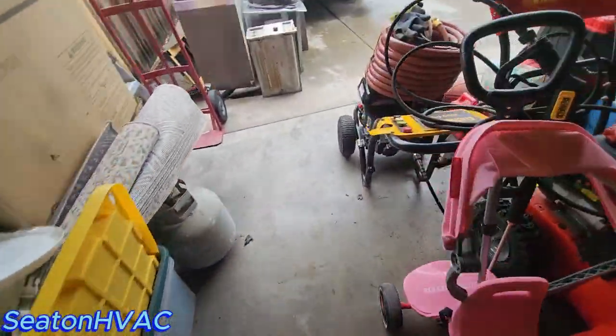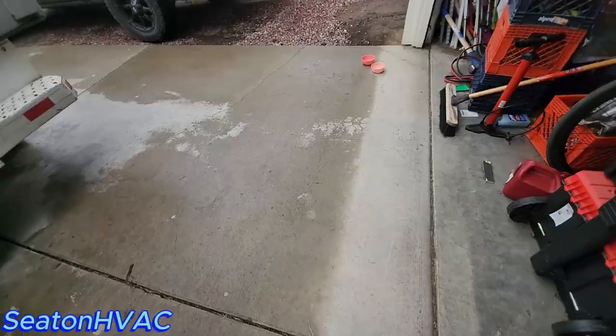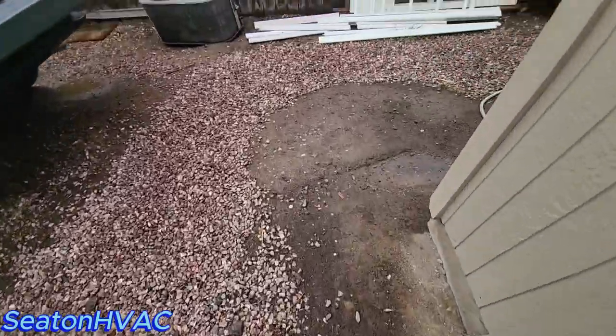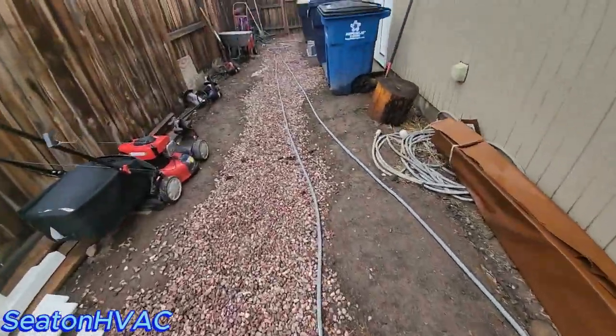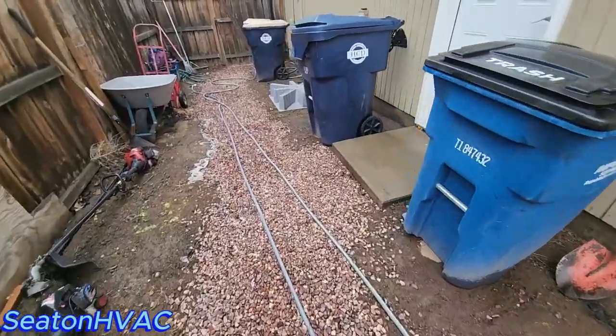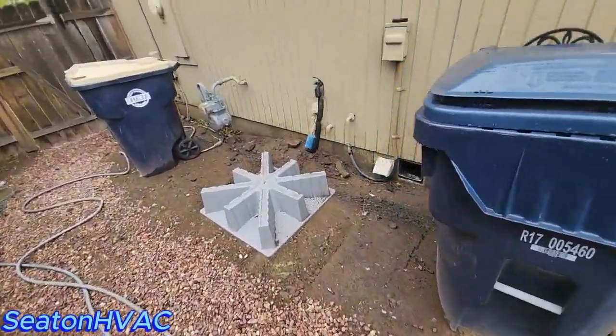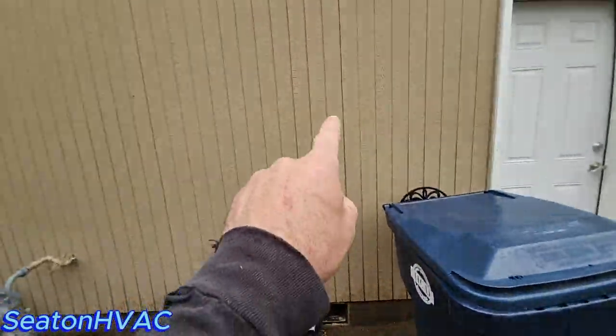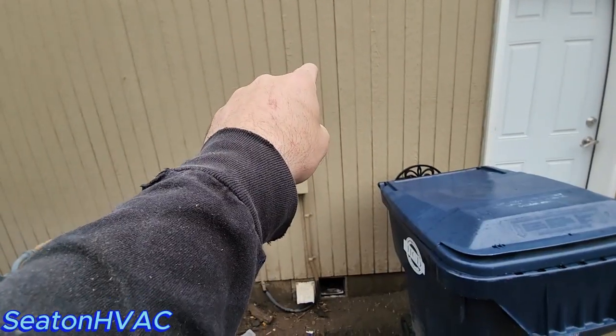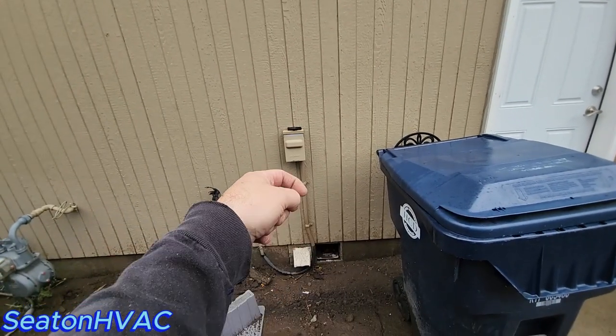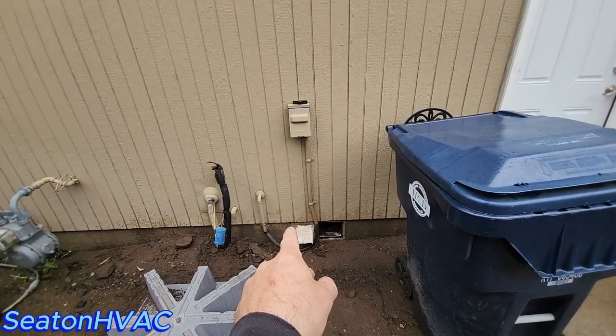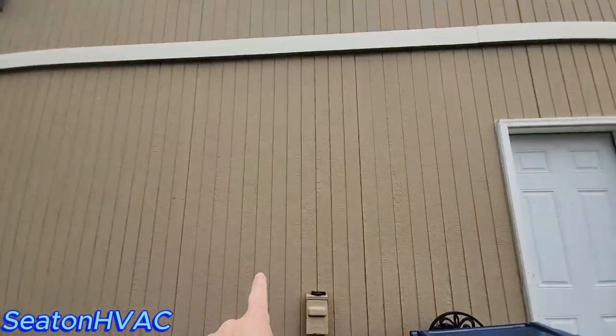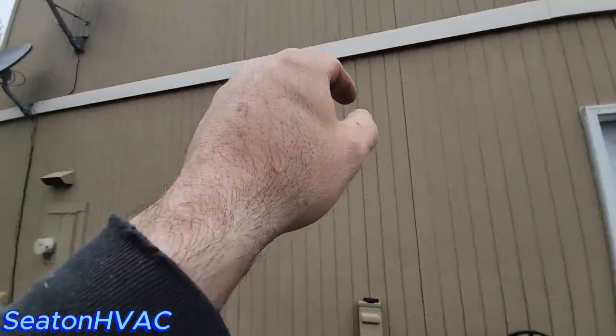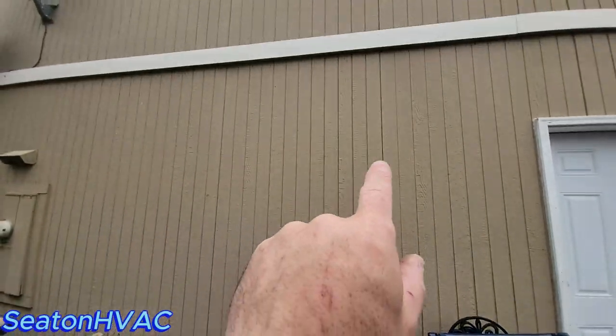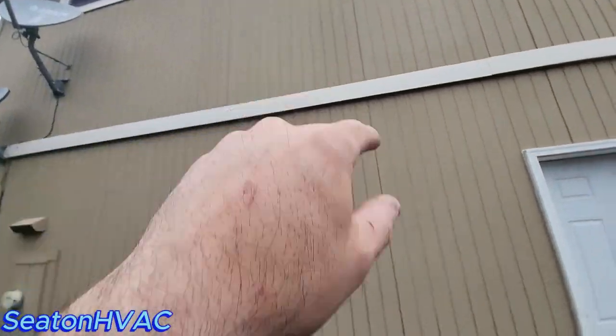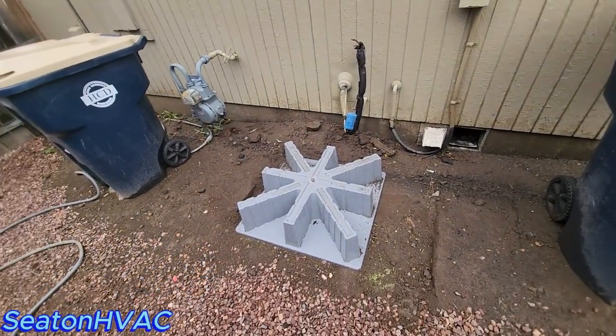So what we're going to have to do to get him a new thermostat wire, because his old thermostat only had 5 wires, is we're going to have to come down from the thermostat, which is in the downstairs hallway. We're going to come down the wall, into the crawl, come out here with some seal tight to get it into the new line hide that's going to be here, and we'll be able to get our 10 wire all the way up to the furnace where it belongs, so we can run this dual fuel properly.